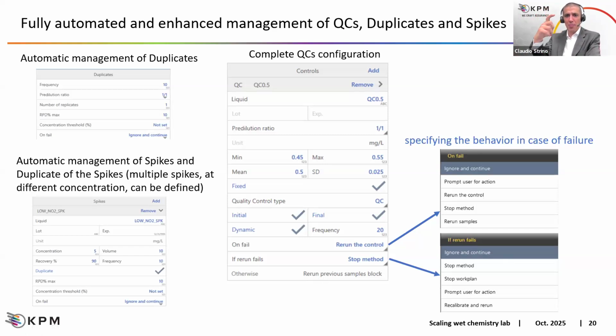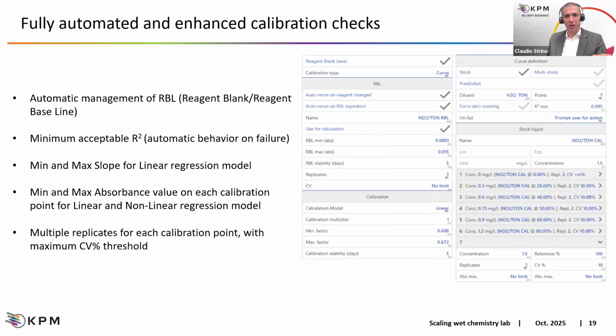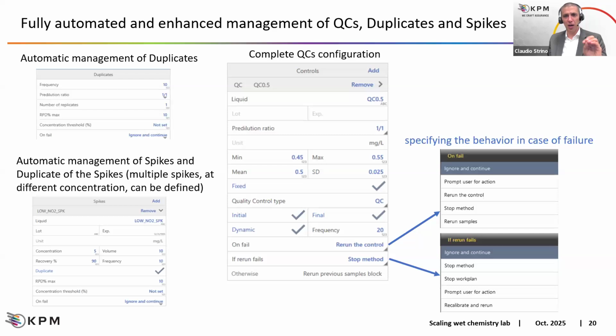In this way, we can be 100% sure that all our sample results are in between 2 QC blocks that successfully passed. And what does it mean, considering the fully automated enhanced calibration check and the fully automated enhanced management of QC, duplicates and spikes? If we have no flag assigned to a test, it means that the results are matching our evaluation criteria. So concerning result evaluation, we are no longer prone to any human interpretation or human error, because for each test, the instrument will apply exactly the same rules and check if the results are within our defined settings for each method.